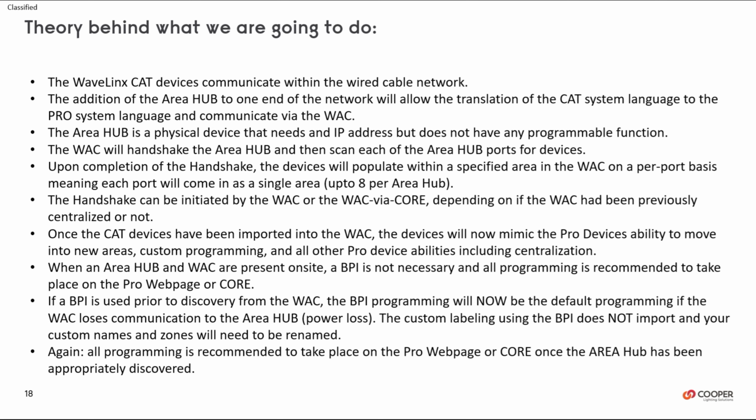When an Area Hub and WAC are present on site, a BPI is not necessary and all programming is recommended to take place on the PRO webpage or core. If a BPI is used prior to discovery from the WAC, the BPI programming will now be the default programming if the WAC loses communication to the Area Hub. The custom labeling using the BPI does not import, and your custom names and zones will need to be renamed. So again, it is recommended to program via the PRO webpage or core once imported.